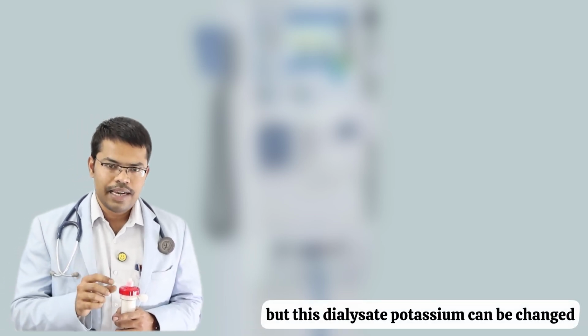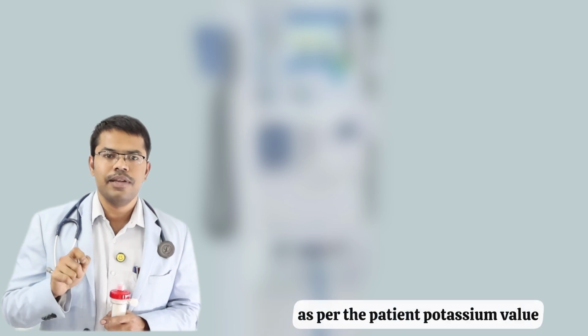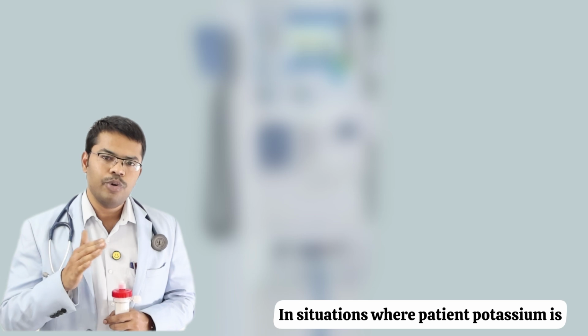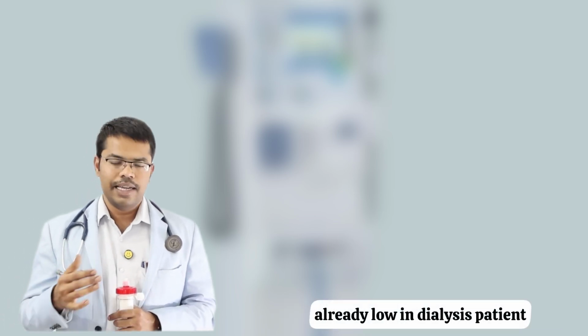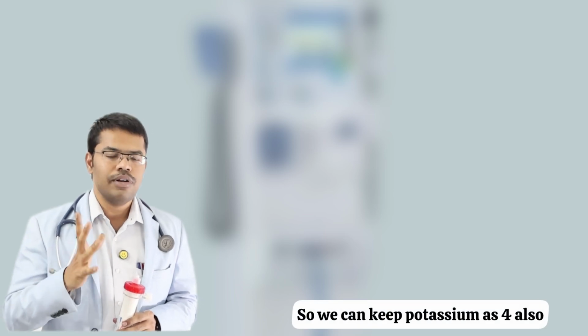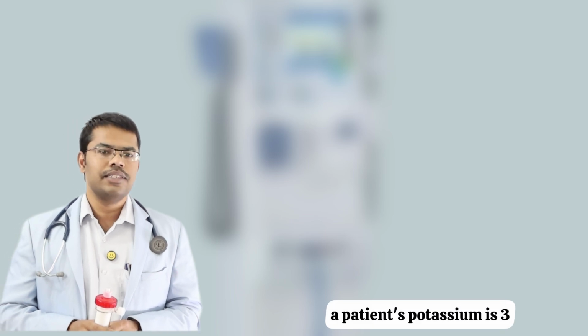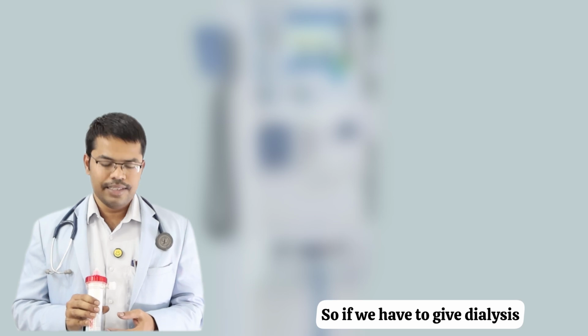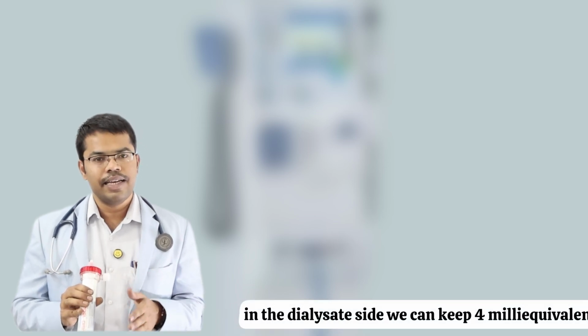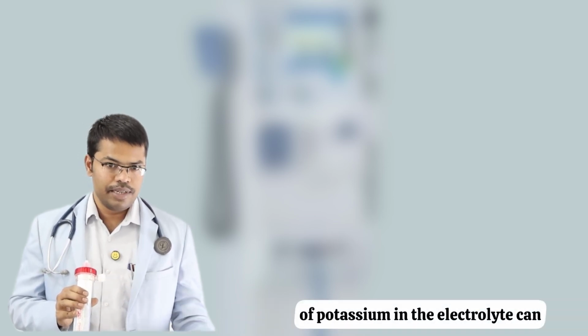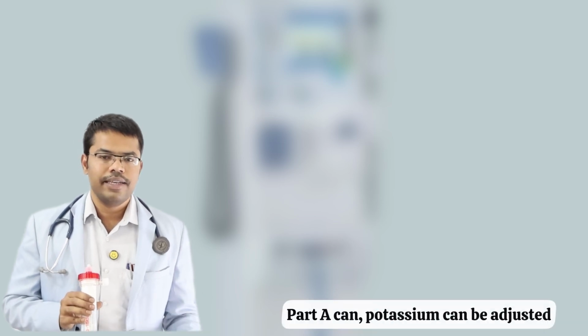But this dialysate potassium can be changed as per the patient's potassium value. In situations where the patient's potassium is already low, we can keep potassium as 4 also. Let us take an example. A patient's potassium is 3. If we have to give dialysis, on the dialysate side we can keep 4 milliequivalent of potassium in the electrolyte can. In the part A can, potassium can be adjusted.